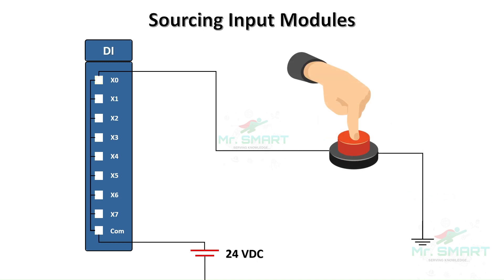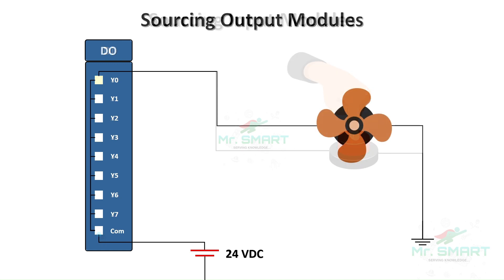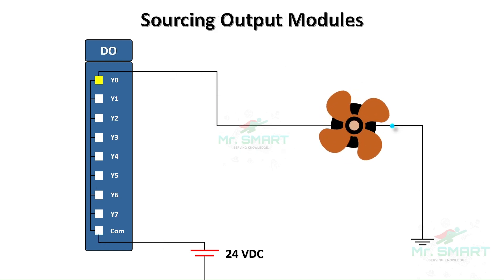On the other hand, a sourcing input module supplies the current to the input device. In this configuration, the input module is the source, and the device, such as a sensor, acts as the sink by connecting to ground. So the input module is providing the voltage to the field device. Similarly, a sourcing output module provides current to the connected load, such as a motor or lamp. It sources the voltage, while the output device sinks the current by connecting to ground.